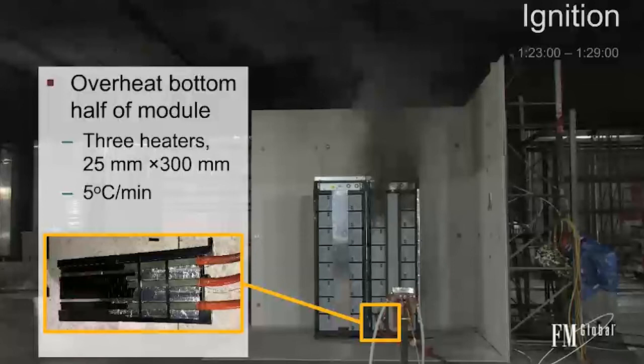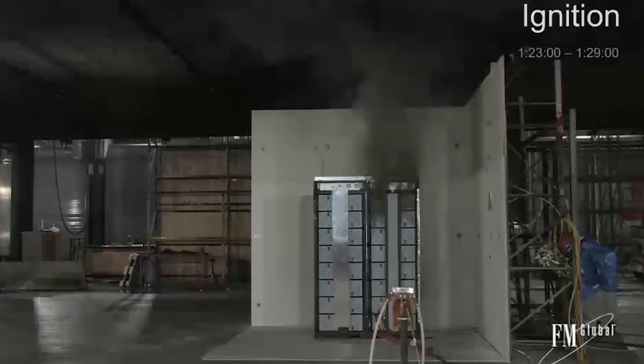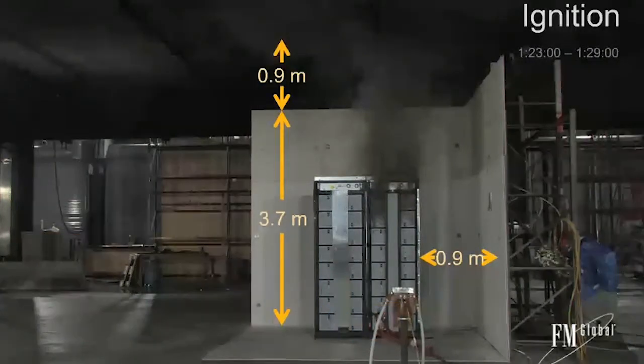So that's why you're going to see some long times between when we turn our heaters on and when we have thermal runaway. I'm physically attaching heaters to the cooling portion of the module, so there's some space separation between the batteries and so on, just to consider. The other thing I want to comment on is the design of the test.